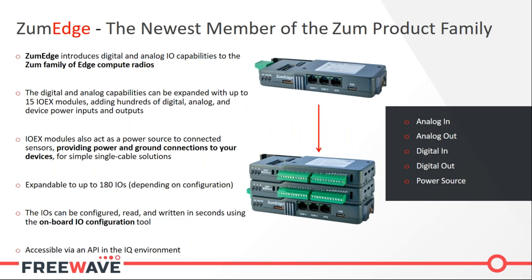The first major feature of the ZumEdge is the integration of IO using the FreeWave IO EX modules. Up to 15 of these IO devices can be connected to the ZumEdge, allowing the user to expand the device up to 180 individual IO points. These IO EX modules can also be configured to power devices, offering a single cable solution for integrating analog or digital sensors. New sensors can be added and configured in minutes.